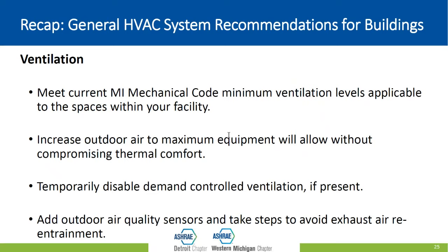So for ventilation, you want to make sure that you're at least meeting the minimum code required ventilation. Sometimes, when we install our equipment, that equipment lasts 15, 20 years, and because it's in the roof or in the basement, very often we don't necessarily think about it. We may not do all the maintenance that's necessary. And over time, the performance of that equipment drifts, right? So we want to make sure that we go back and make sure that we are getting what we are supposed to get out of our ventilation system. Are we at least meeting code minimum in terms of the ventilation levels for each individual space within our building? And the required levels vary based on the type of your building and what it's used for, right?